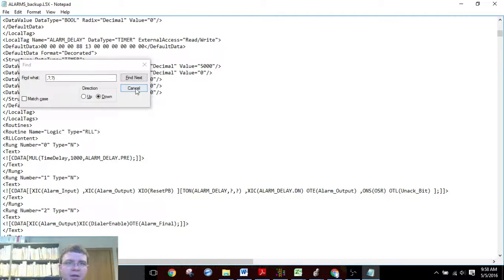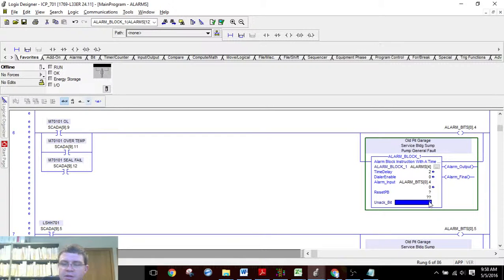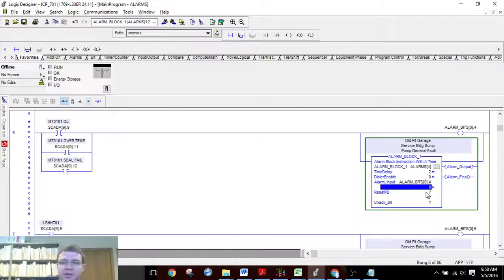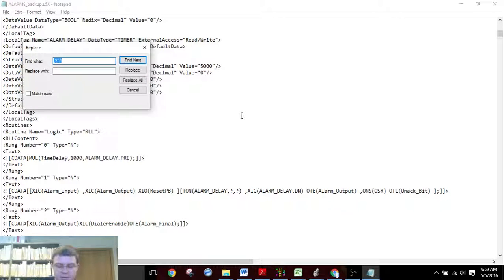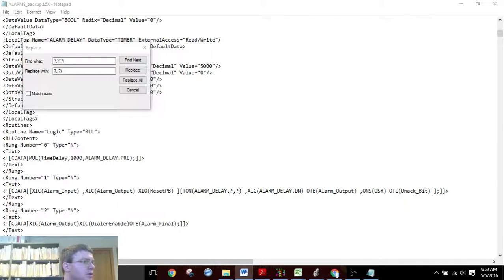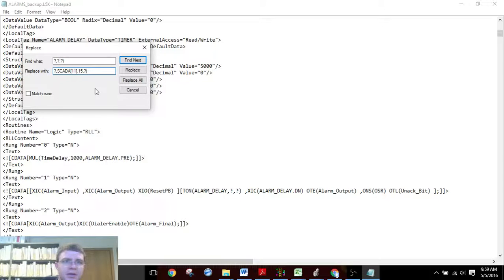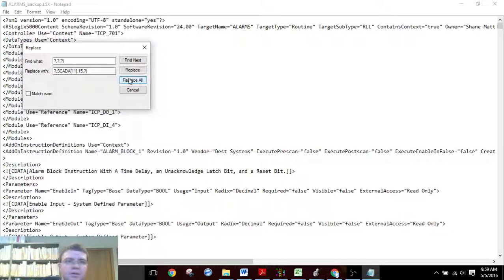We will replace the middle question mark because there are three different tags that need to be inserted into each of these add-on instructions, and the reset button is the middle one. So we are going to Find and Replace, starting with the three-question-mark ones — those are add-on instructions that have none of those three required tags inserted into them. We'll copy, paste, and replace all of them.